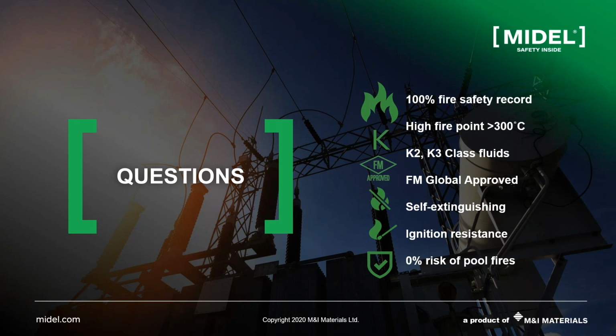We don't do that. The reason with circuit breakers is they rely really on a mechanical movement. So the breaker needs to break and make. Esters have higher viscosity, and so during this make and break movement, the parts will face more mechanical resistance, friction from esters. So they will become slower. And when I say slower, it's a very, very tiny increase in time. This will cause a sustained arc when they make and break, and so erode the electrodes. As such, esters are not really used in circuit breakers.